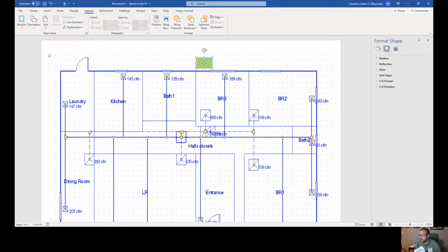If not, if you go from one end or the other, which happens a lot, my house is actually done that way, that it kind of goes from one end all the way to the other, your duct will be a lot bigger because it has to carry everything. So by making it in the middle, most of your duct can be smaller because it only has to carry half. So what does that look like? Well, I'm going to just come down here and I'm going to try to split this.